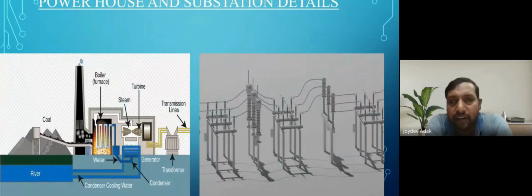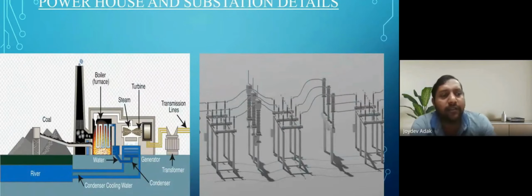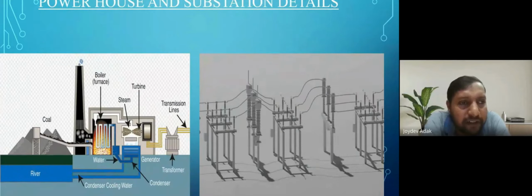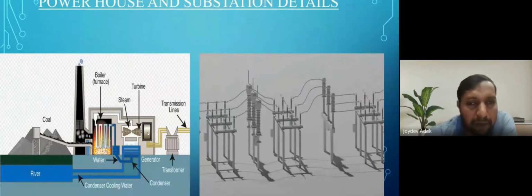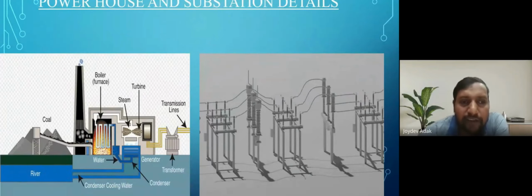Now, if we consider the different types of fault, this is the schematic of a thermal power plant. I'm starting from the coal handling plant to the transmission line, that is, the switchyard. The last one is this one, the transformer, and this is the coal handling plant. Several equipments are here. From the coal handling plant to the boiler, the boiler evaporates the water, and that steam goes to the turbine and rotates it. The turbine works as a prime mover for this generator. The generator, based on the turbine and the excitation from an external DC source, is called a turbo generator or alternator. This generates supply, and the supply goes to the transformer, called the generator transformer.